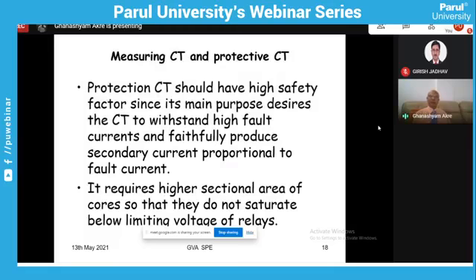Protection CT, as I told you, should have a high safety factor. That means it should allow the secondary current to increase faithfully in proportion to the primary current for the protection system. That is why this core has a high cross-sectional area, because the core should not get saturated. It should allow the flux density, and it must have a high cross section. So it is larger in size, while the metering core is smaller in size.